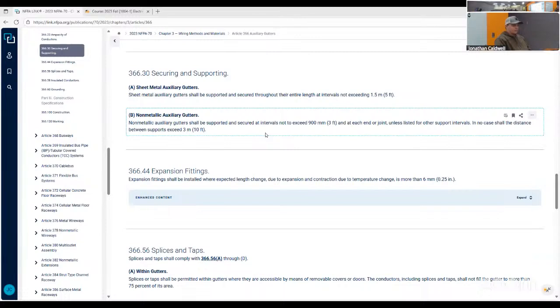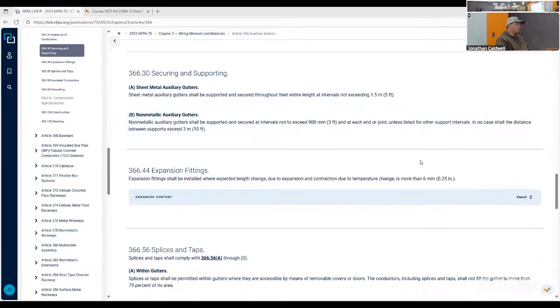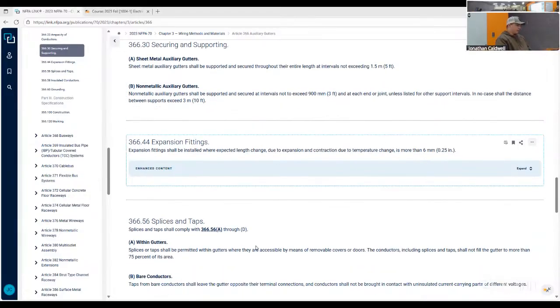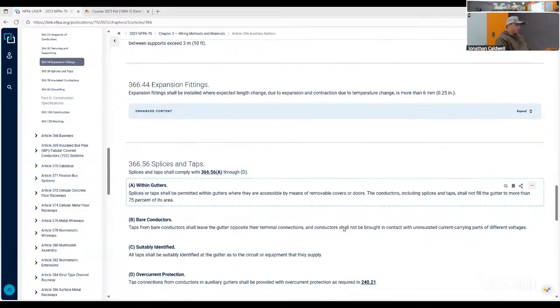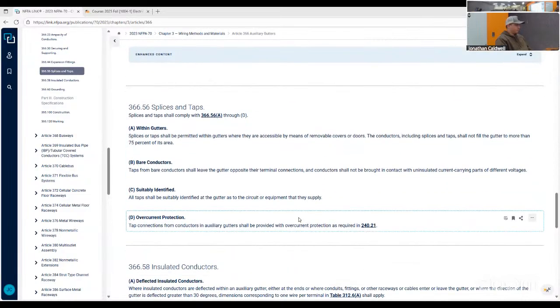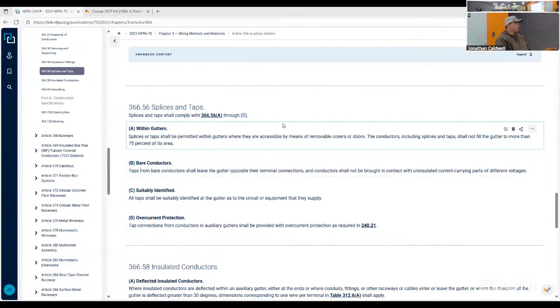Even though code says you just do every 5 feet, should you do every 5 feet? No. That's a great example of it. They do make expansion fittings for gutters. Have I ever used them? No. Do I think you should ever have to use them? Probably not, unless you're doing bus duct.